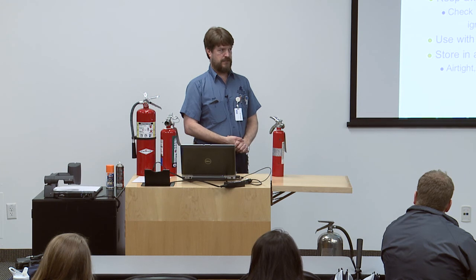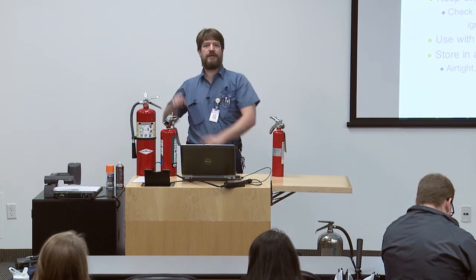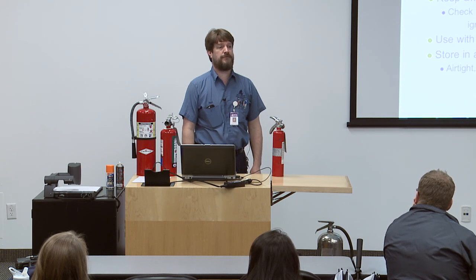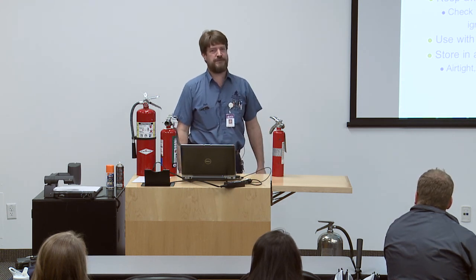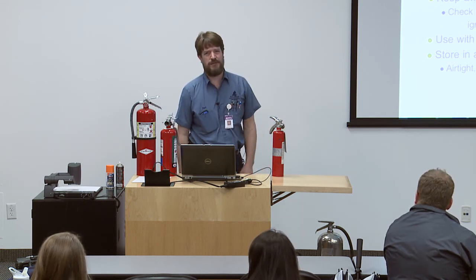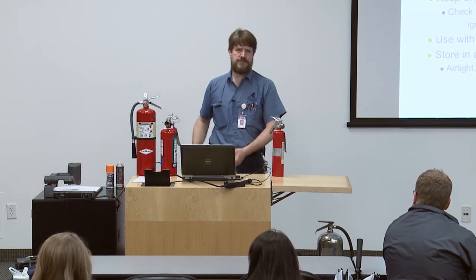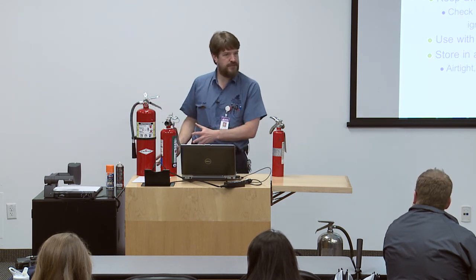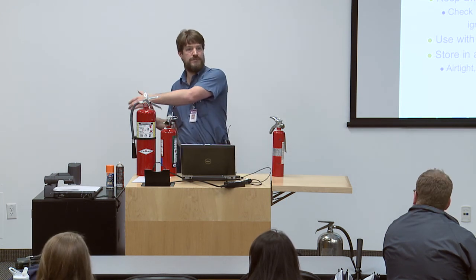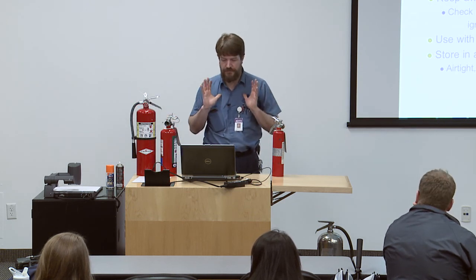So I said, okay, I've got a solution. Switch them around. Now that's a storage, and that's electrical. And she goes, well, if it's okay with the building inspector, it's okay with me. Went downtown, talked to the building inspector, called him first, went down there, and he says, I don't care what you name your rooms. I said, good enough. So we switched the signs. That one's storage now. So we put all of our flammable storage in the ones that don't have electrical panels in them. The ones that have electrical panels, we can't have any flammable stuff in it, but we can store non-flammable stuff as long as it's 30 inches away from the electrical panel. So those are the rules.